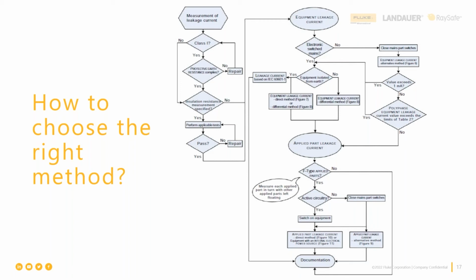So you would be right to choose the direct method, except when the medical device has no on-off switch. That means that when you plug it into the wall, it is automatically on. There's no off button. So in that case, we're required to use the alternative methodology. So we're not going to go into a deep dive on this decision tree and how to use it right now, but I want you to know this comes directly from the standard. And we do have a webinar in which we actually go step by step through this decision tree. And I suggest that you look for it and that you listen through the explanation.